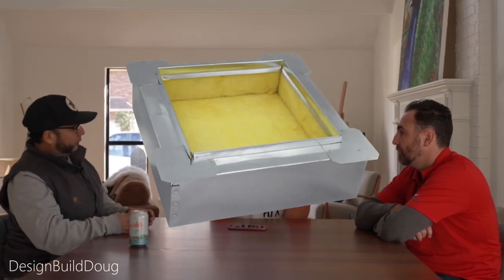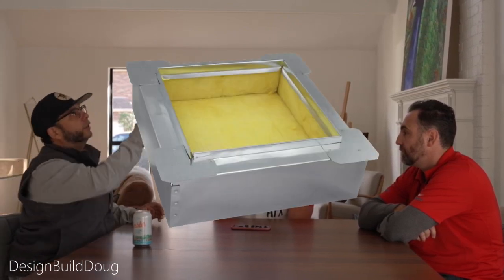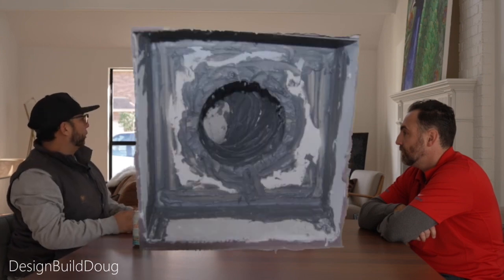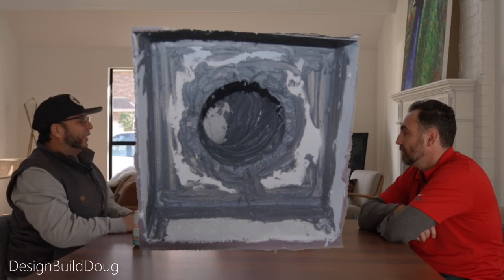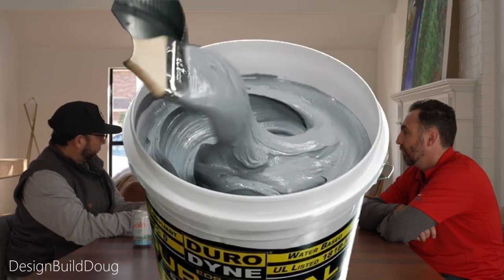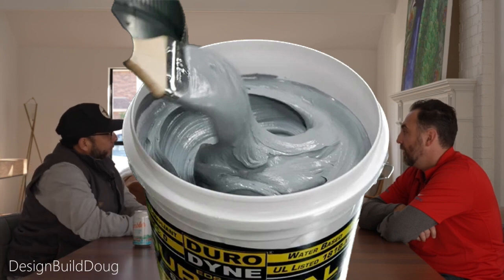Now, when I'm coming to an area where I have, let's say, a 2-story home where I cannot get to the ductwork in the subfloor area, if I'm exposed with a bucket or boot and the homeowner does not want to cut sheetrock, we will seal the inner liners or inner side of that boot with actual mastic, sealant, or what we call 'pookie' in our industry. It's just a sealant that goes on and seals up those surfaces so they lock in.